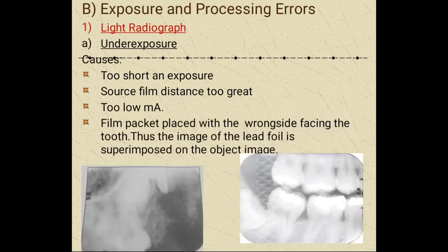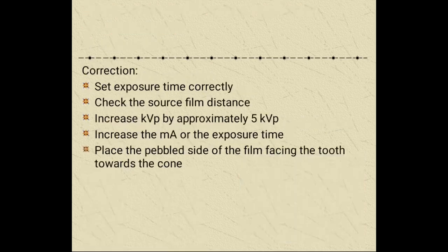Moving on to exposure and processing errors: a light radiograph is due to under-exposure. Causes include too short an exposure, source-film distance is too great, too low milliampere, or the film packet placed with the wrong side facing the tooth — causing the image of the lead foil to be superimposed on the object image. We can correct it by setting the correct exposure time, checking the source-film distance, increasing kVp by approximately 5, increasing milliampere, and placing the pebble side of the film facing the tooth towards the cone.